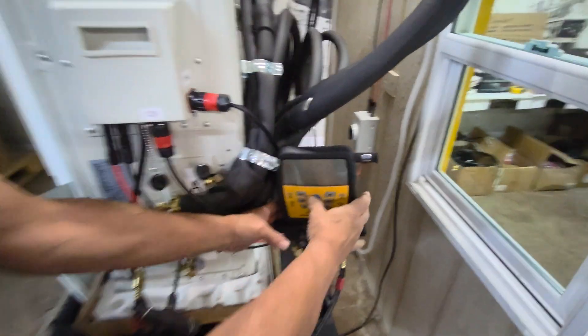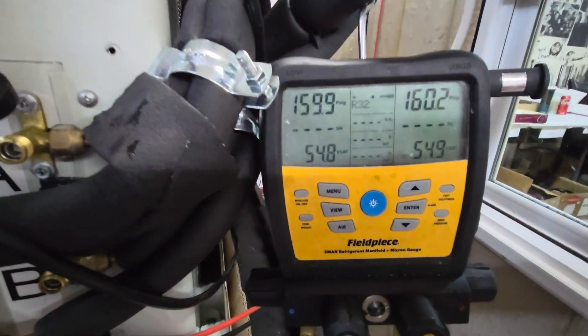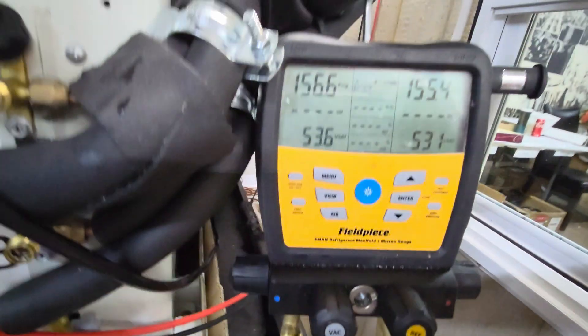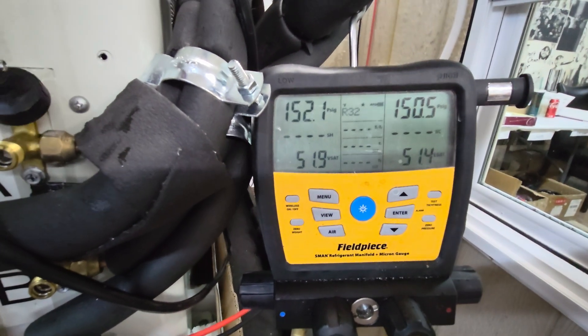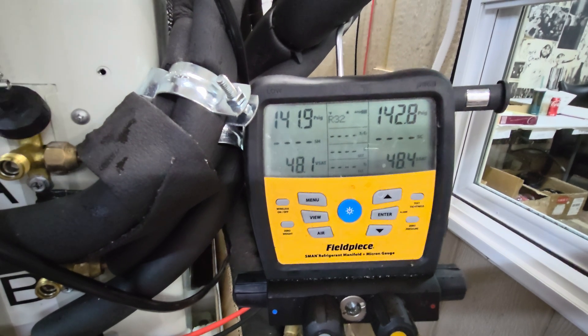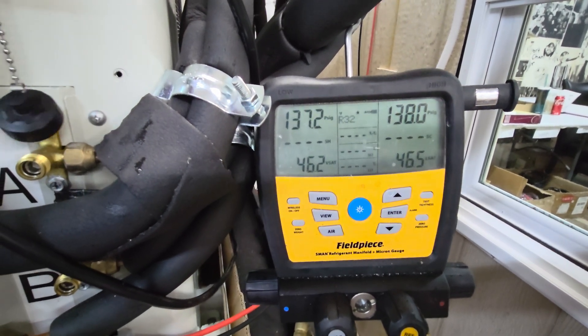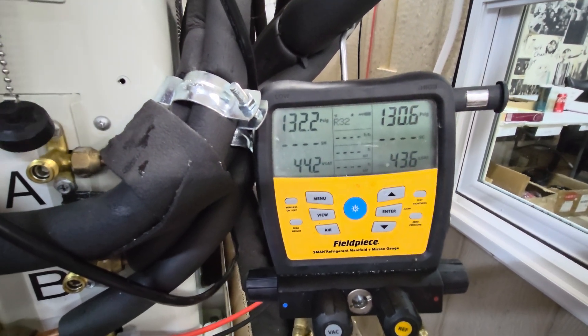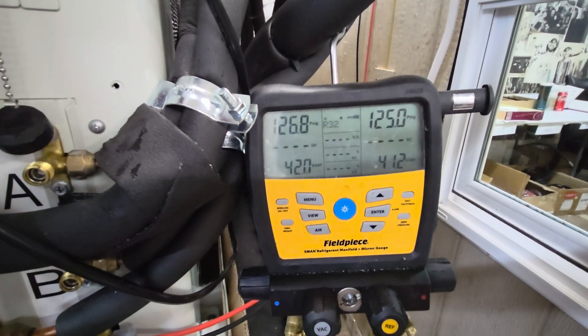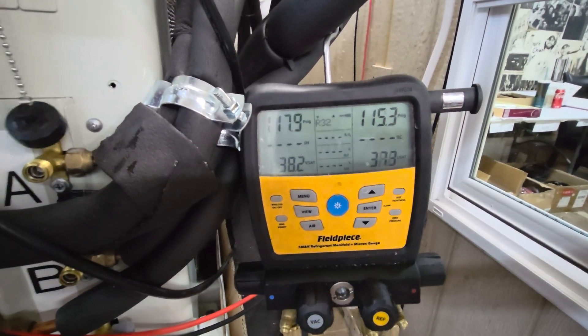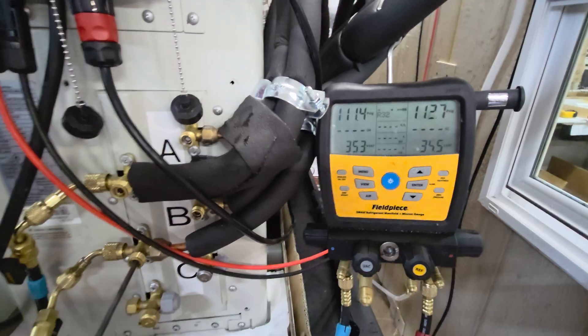Dropping. This is a two-ton unit, so it's going to take a little bit longer than the one-ton units. As it gets closer to zero, start closing the valves that way you don't have to turn so far. See how they're staying pretty much the same?